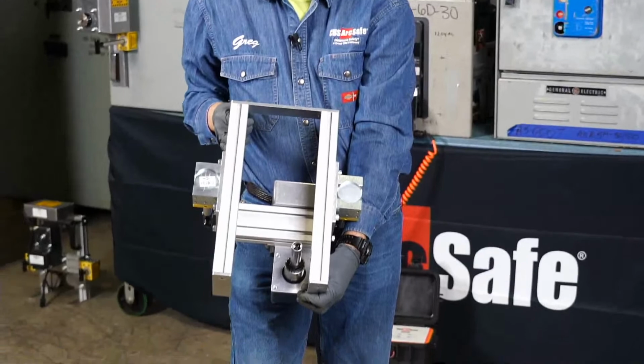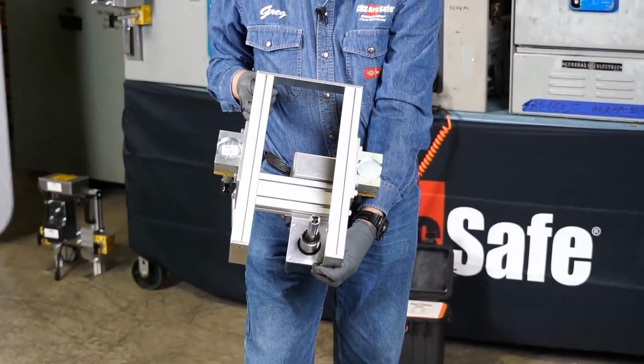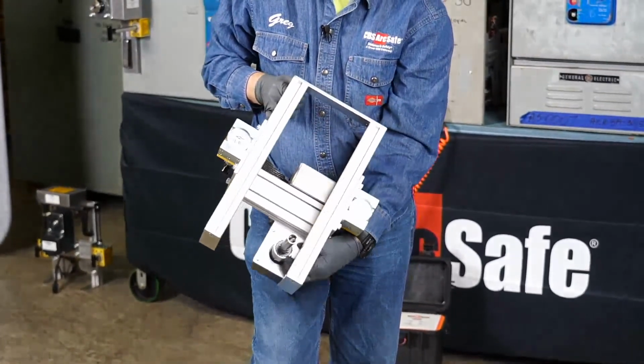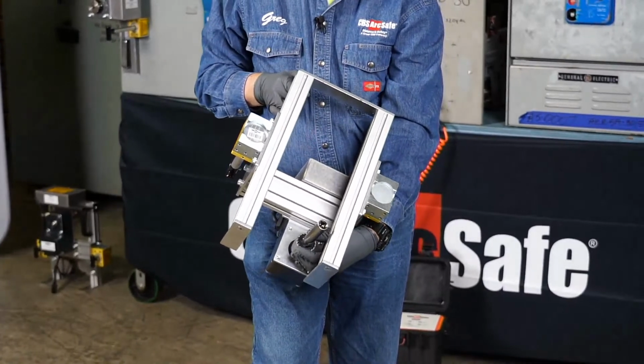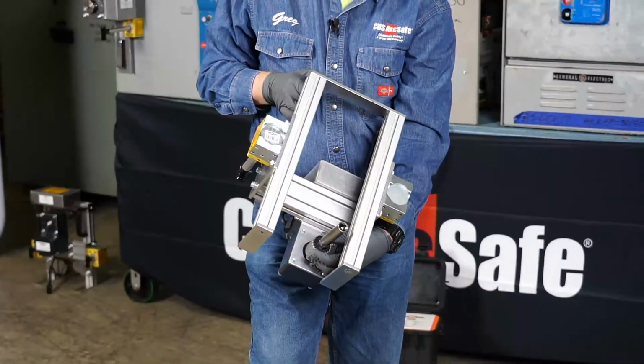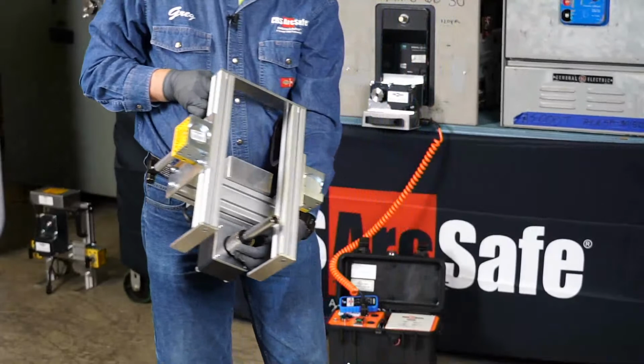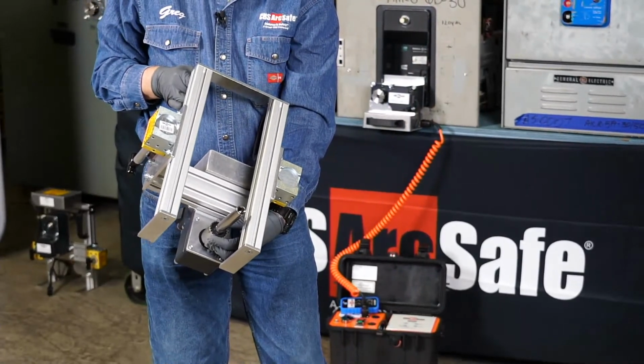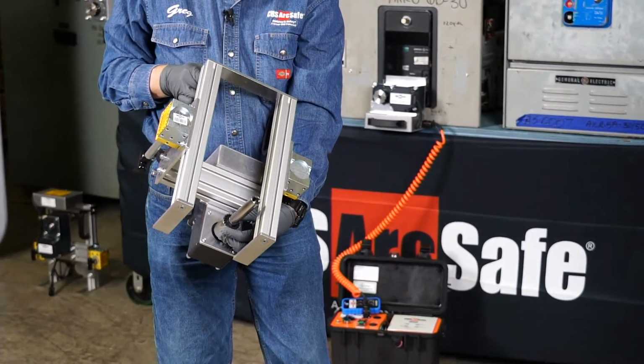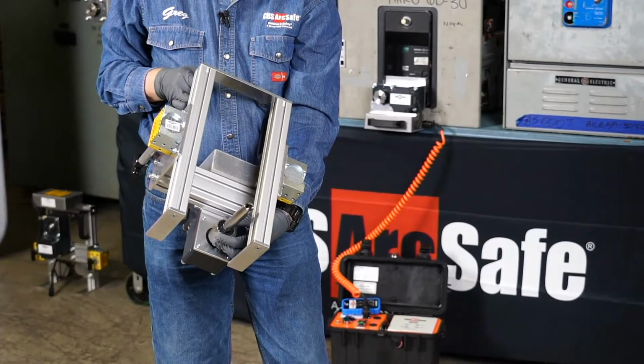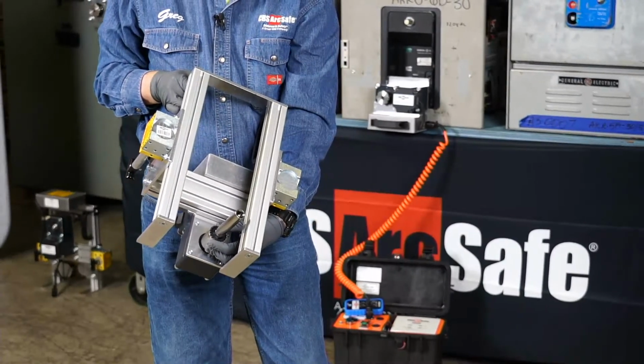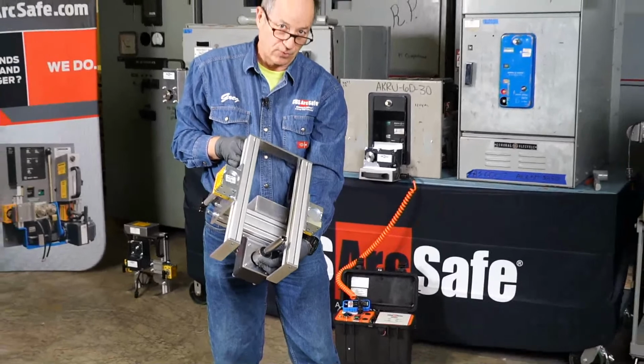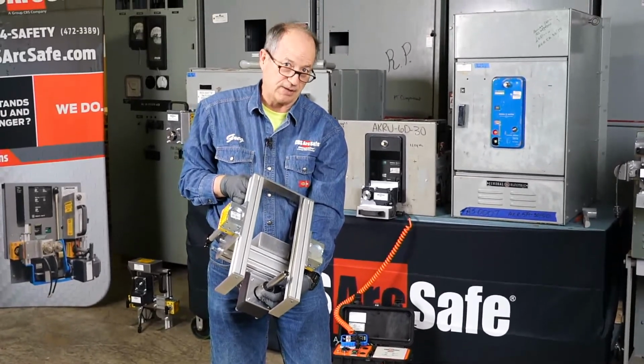We use two protection mechanisms for the circuit breakers: whether we use a torque clutch with a slip disc in it, or whether we use a perfotorque. This is a mechanical device set up with a limited amount of force we're going to let it generate before it clicks and makes noise to let you know you're trying to use more force than what you should be using to rack this circuit breaker.